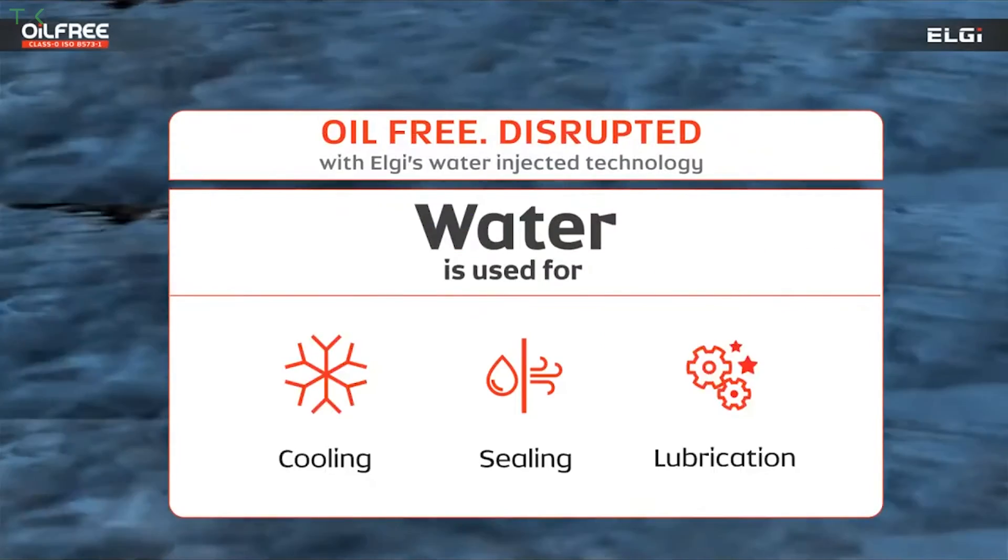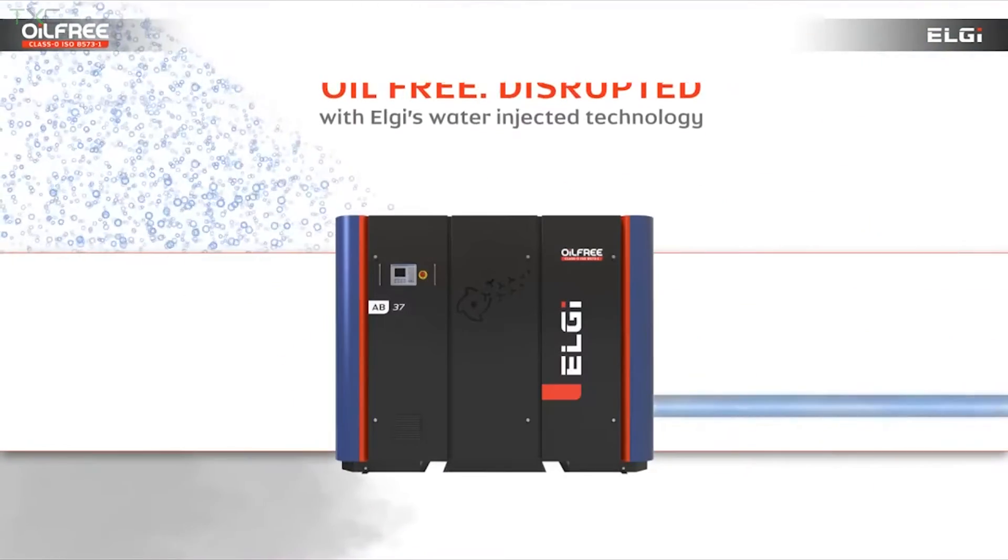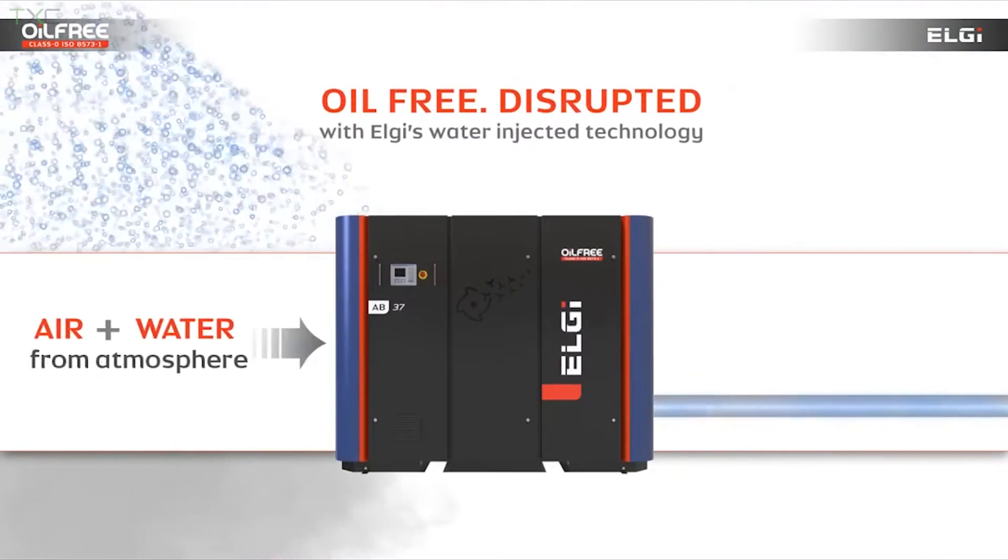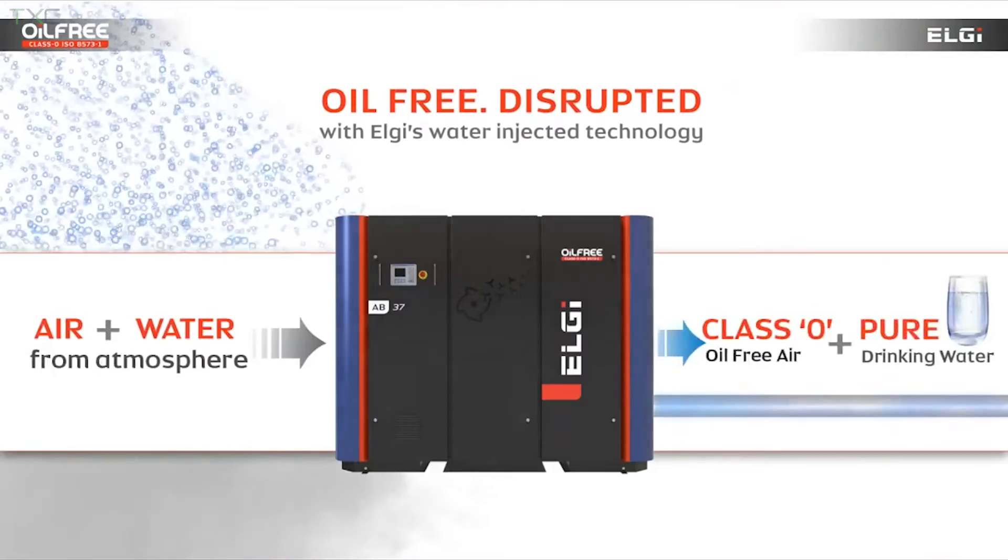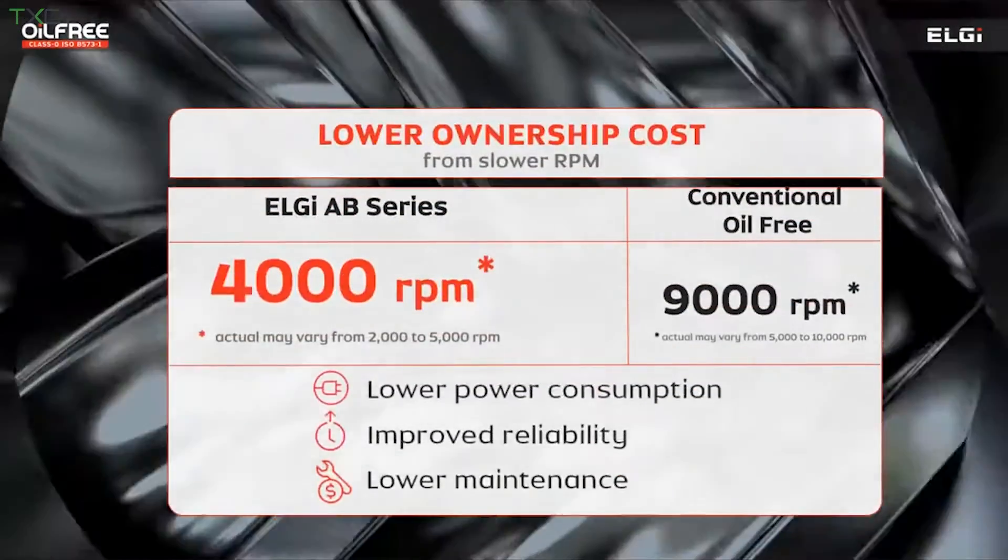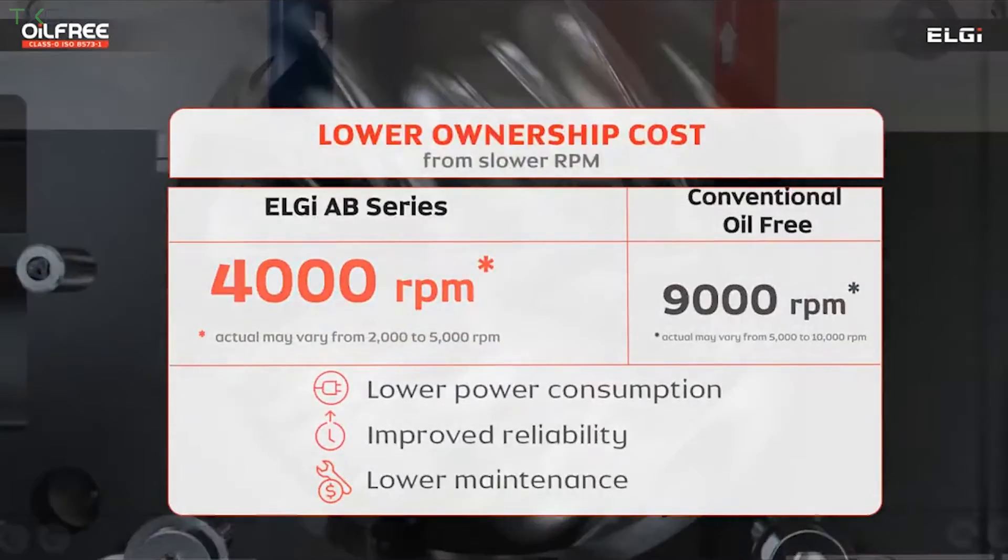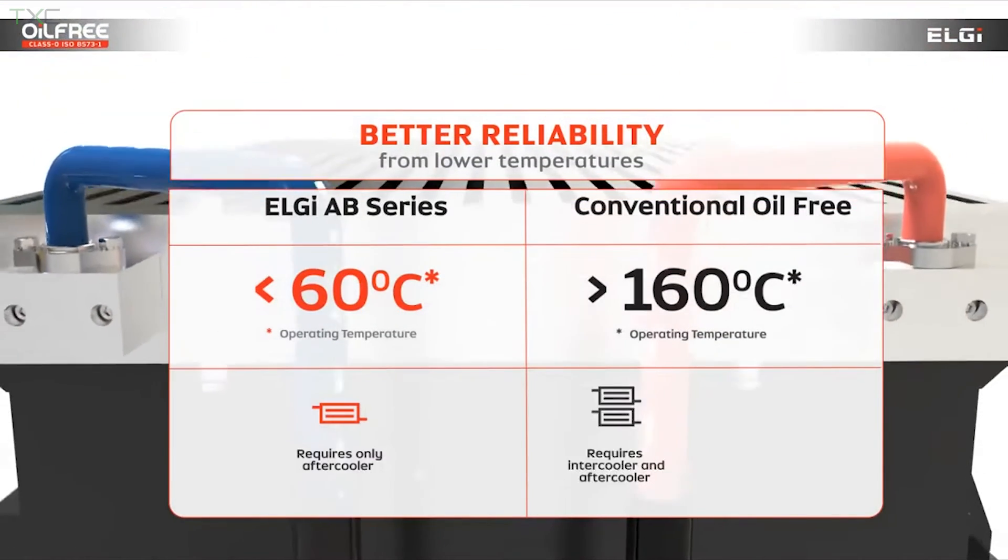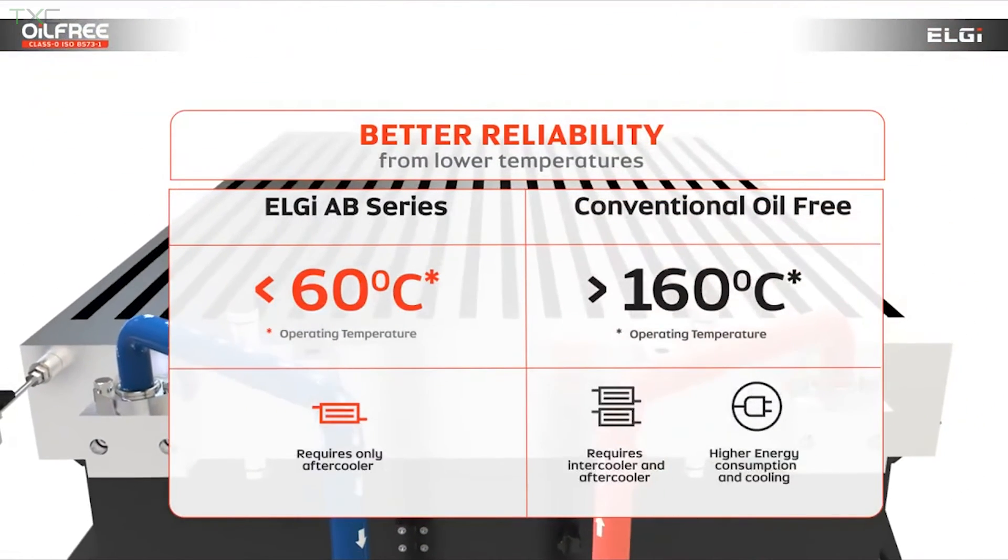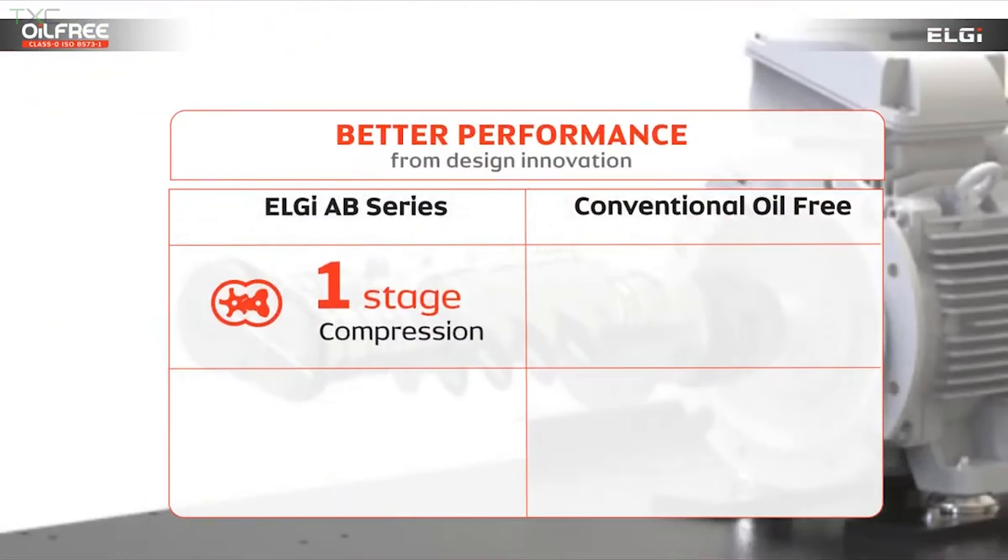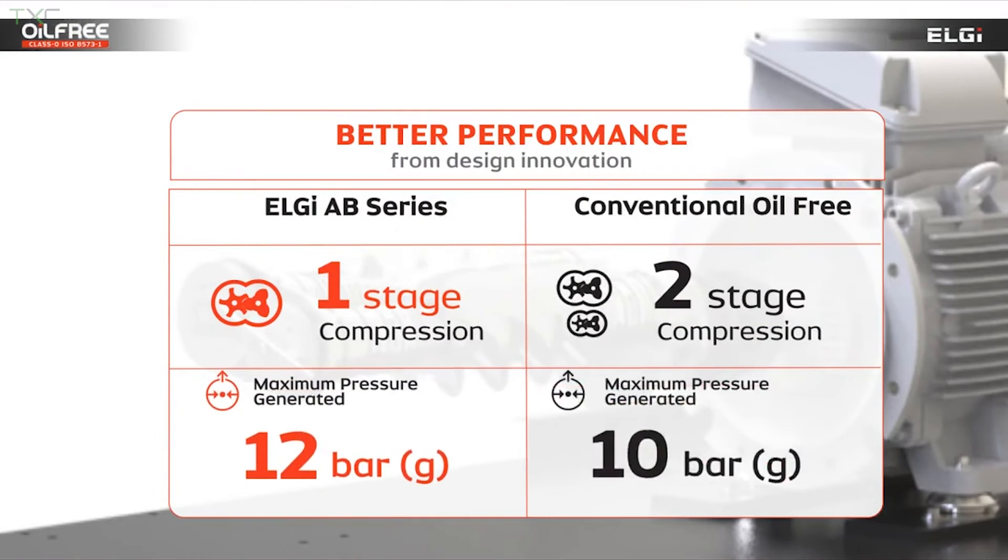You get it for less input power. So as a customer, you have to be thinking, well, if I'm up north where I'm paying a massive amount for power, I'm going to have to pay more to put in an oil-free compressor. It's not just that an oil-free compressor costs more to begin with. Now my power costs are more. But then on the flip side of that, if you have more cleanup equipment, it creates a pressure drop across this cleanup equipment that your compressor has to overcome.